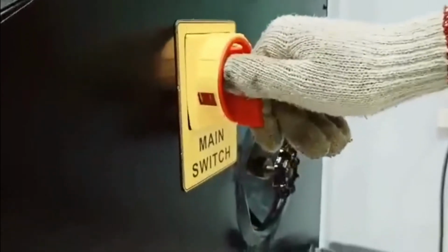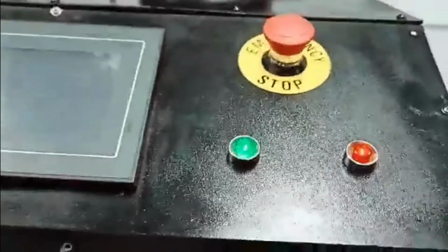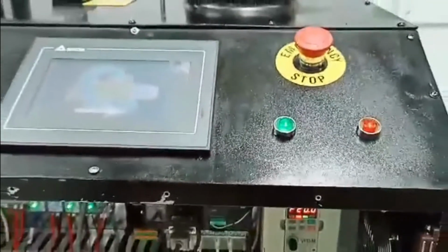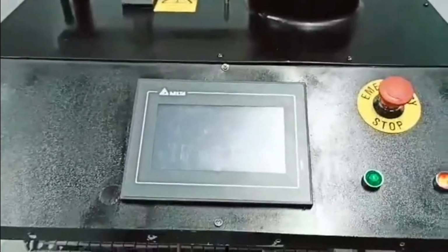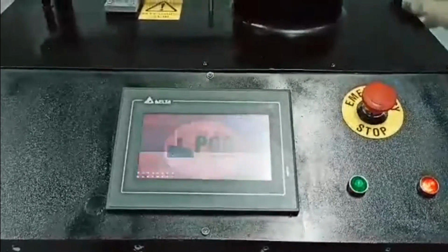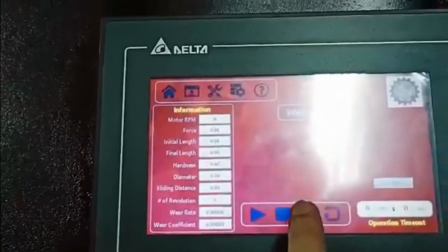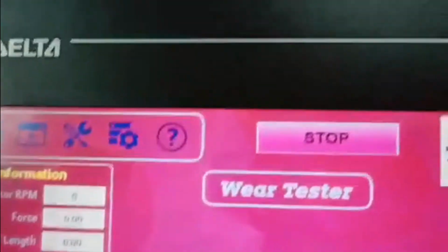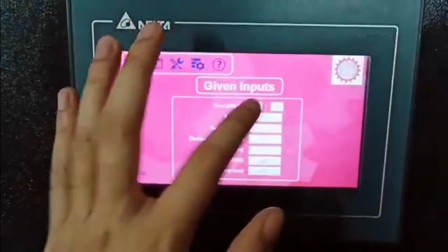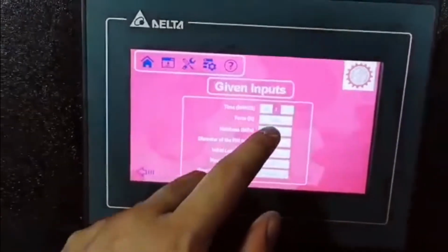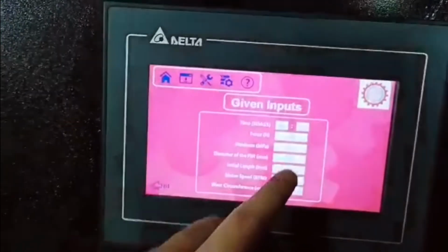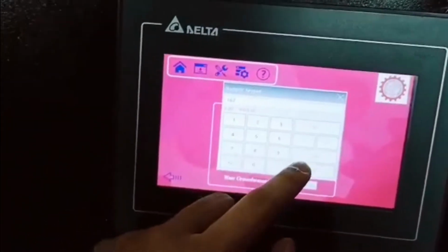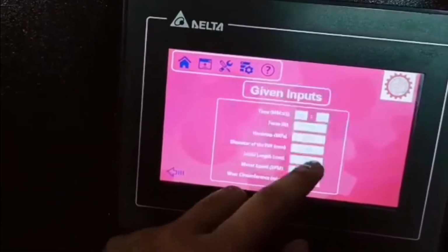Make sure to switch on the circuit breaker and flip the main switch to turn on the wear tester. You will notice that the indicator lights are blinking. This is an indication that the machine is ready to operate. Press the reset button to refresh the program and click the initialize button to set up a new testing. This will bring the actuator up to support the lever arm. We can now input the data needed to start the activity. The data needed are the force, hardness, diameter, initial length, motor speed, and wear circumference, which in our case is 80 pi or 251.33.